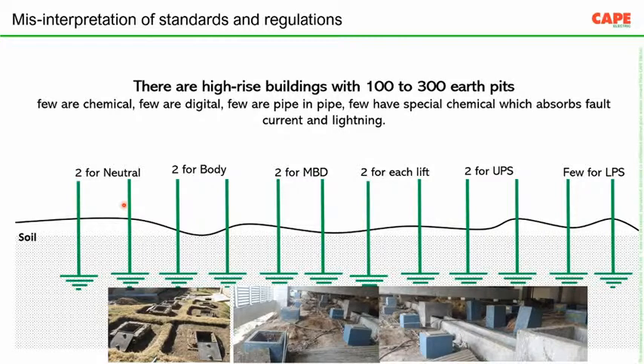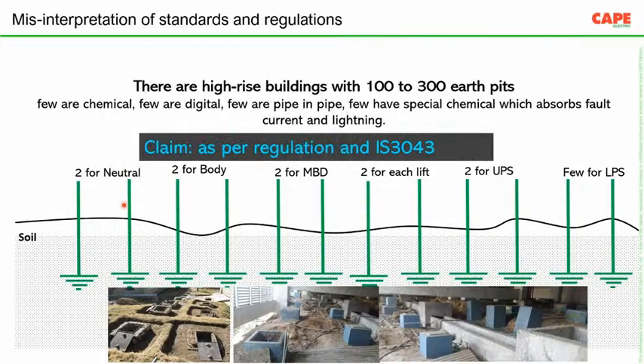And some of the earth pit vendors even say that I have a chemical and my chemical will absorb the short circuit current. My chemical will absorb lightning current. Actually, all these claims are wrong. IS 3043, neither the standard nor the regulation has written in this fashion. So this is a misconception.